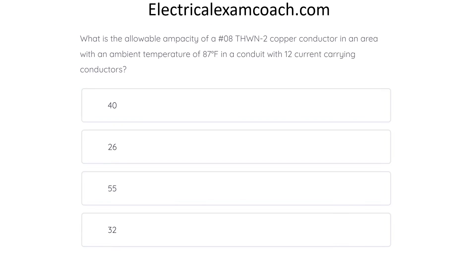What is the allowable ampacity of a number-8 THWN-2 copper conductor in an area with an ambient temperature of 87 degrees Fahrenheit and a conduit with 12 current-carrying conductors? The correct answer is 26 amps.